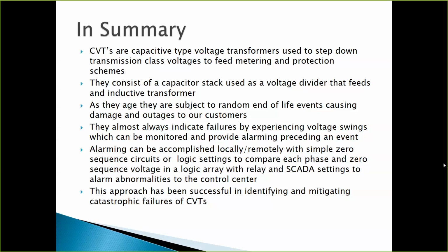I'm not really a relay P&C guy. I have an interest in it, but it wouldn't be my discipline. But I know that there is a pre-canned setting with the SEL relay, so I suspect it looks at all three voltages and does the math for you. That would be my guess. But we could find out from the SEL manufacturer's bulletin if we need to. And the relay does detect a small zero sequence voltage. It does give an alarm. It absolutely works for a zero sequence issue on those SEL relays. I've seen it. I'm not exactly sure of the mechanism by which the zero sequence is done in the relay, but I strongly suspect it's a math function provided from the inputs of the voltage.